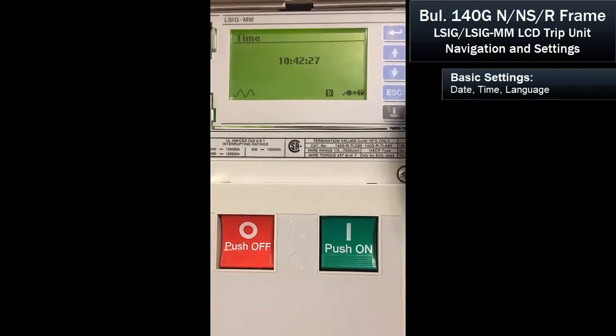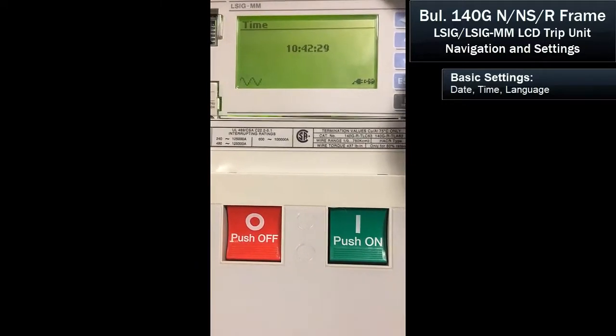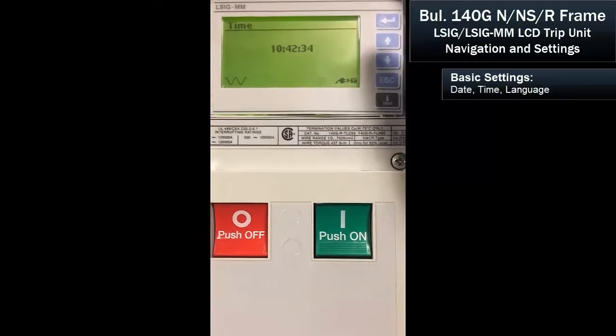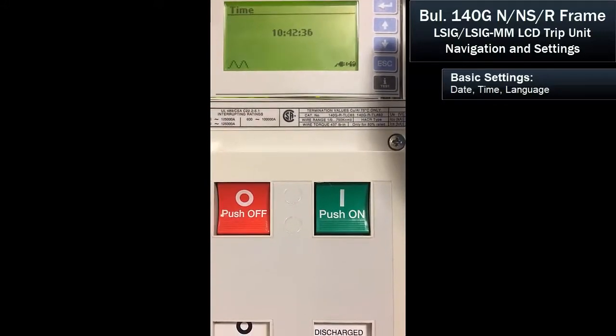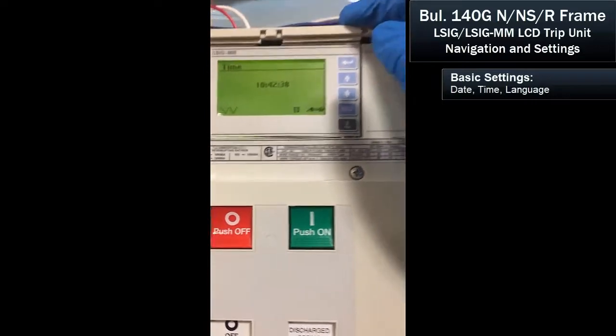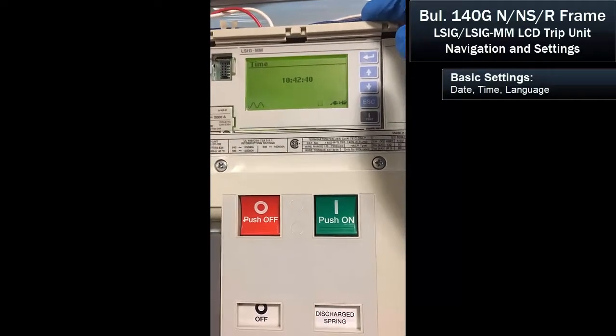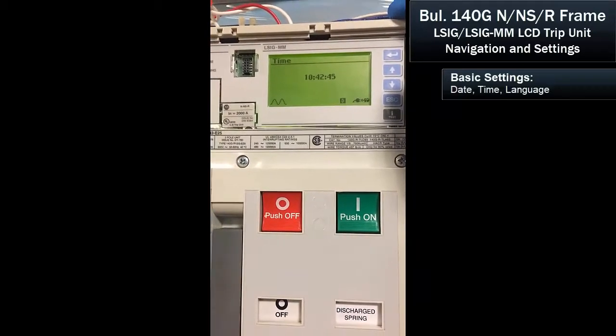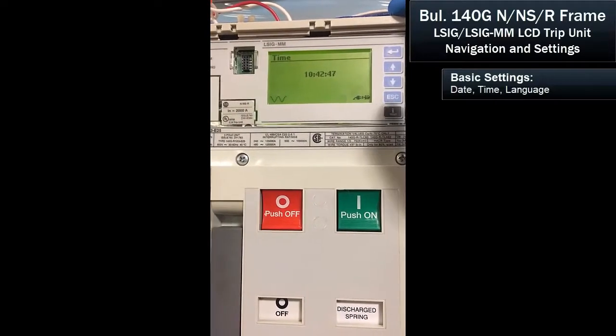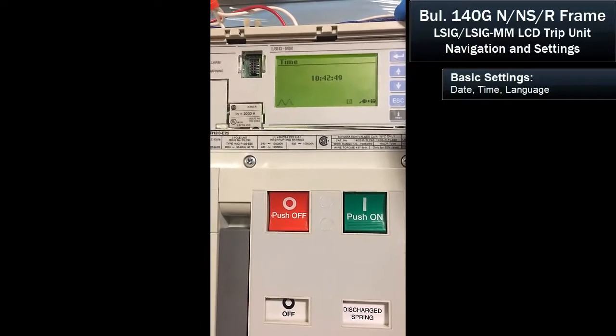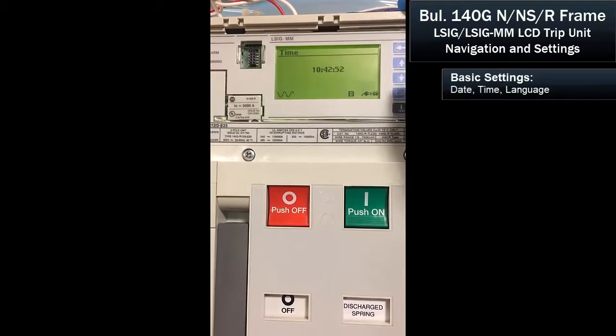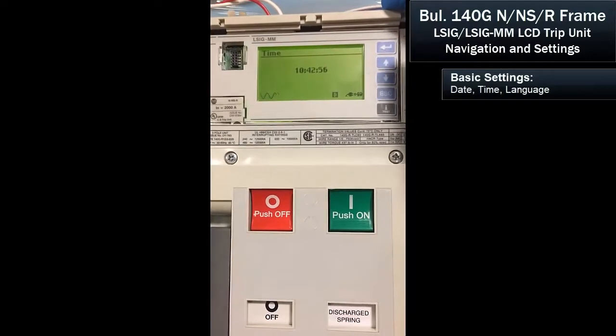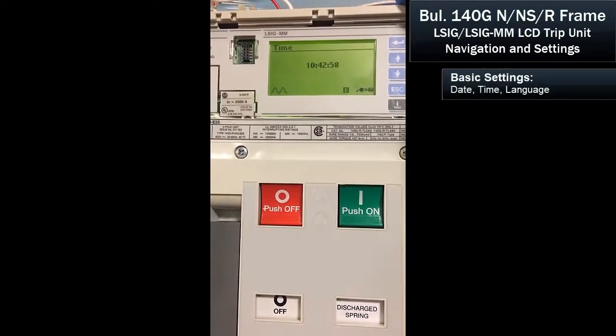Now it's important to remember that these settings will only hold in the device while it's powered. So upon startup or installation in most MCCs, the product has a 24-volt power supply connected to it. Once you apply power and keep power on that 24-volt circuit, all of these settings will remain the same — at least the time and the date. All the protection settings will stay stored within the breaker.